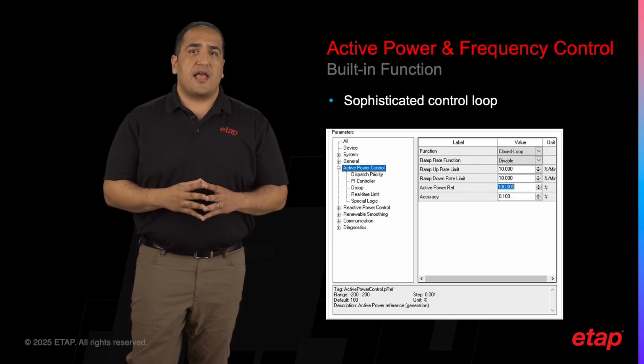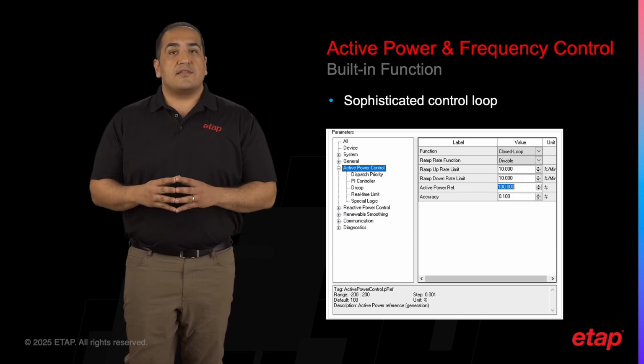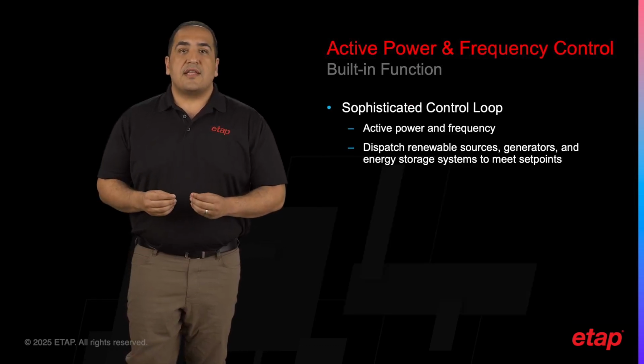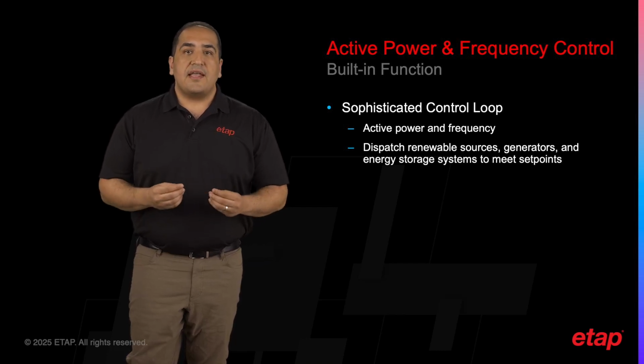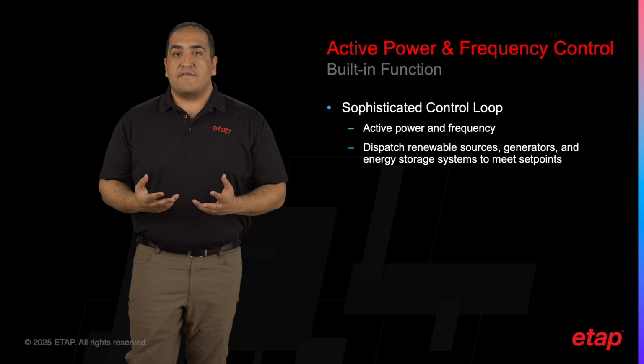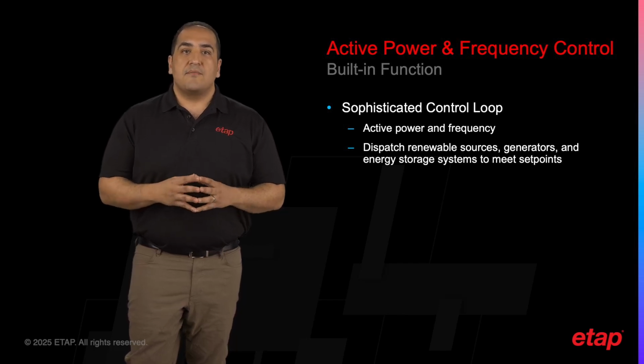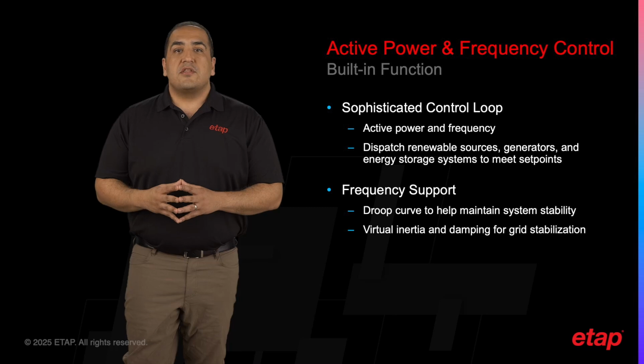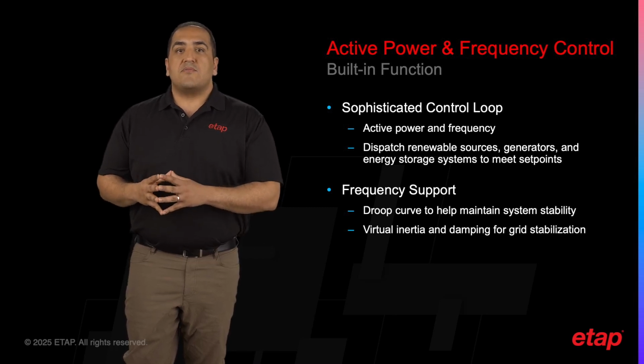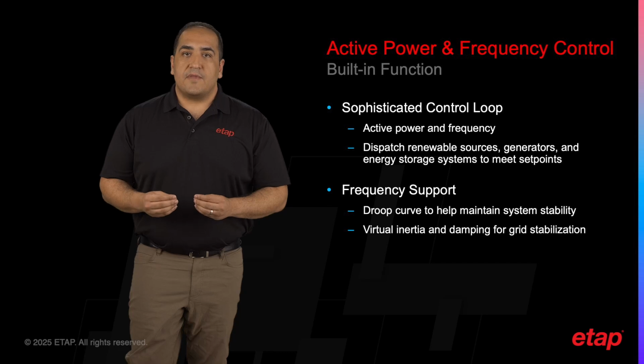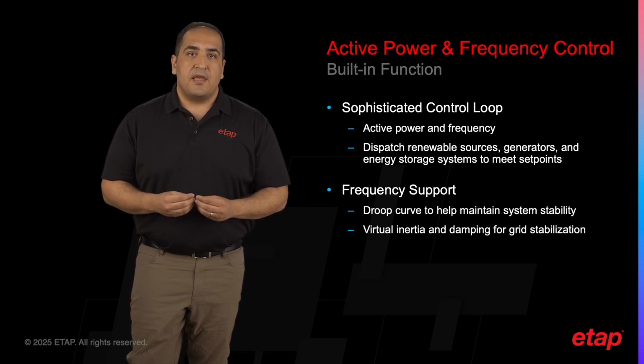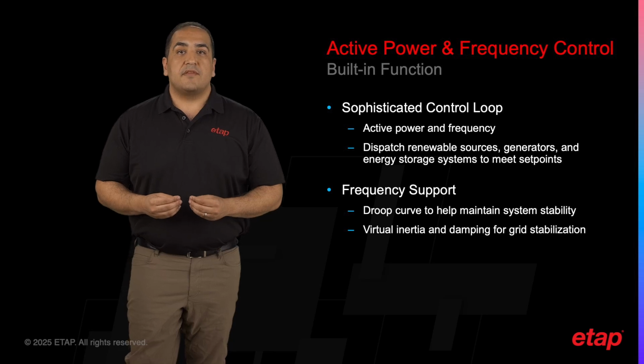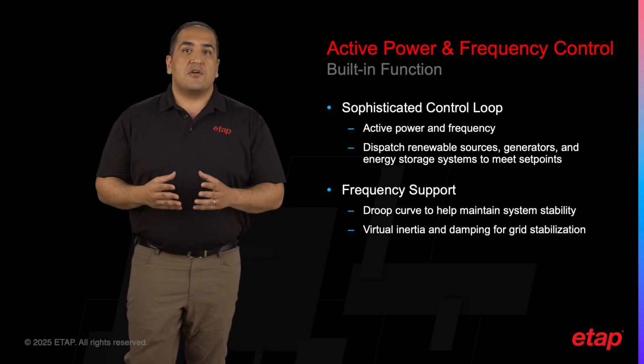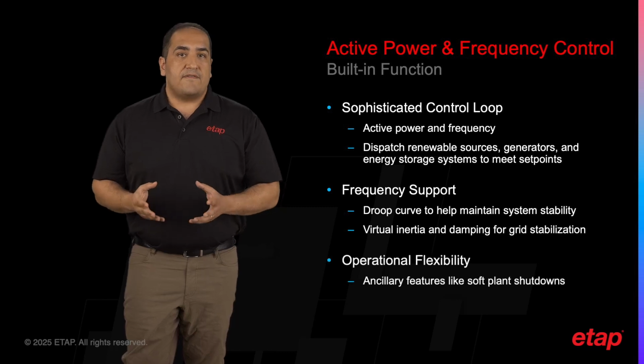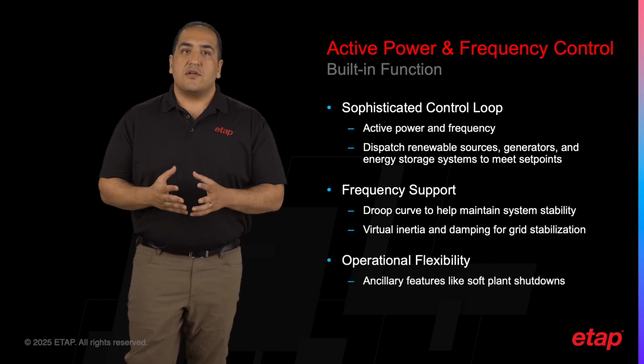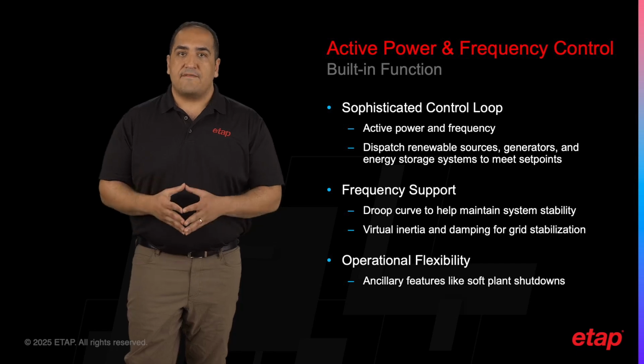EPPC excels in managing active power and frequency through a sophisticated control loop. It ensures that renewable resources, generators, and energy storage systems are dispatched effectively to meet the set point at the plant's point of interconnection. This function not only tracks the set point, but also provides frequency support using a droop curve, which helps maintain system stability. Additionally, EPPC can implement virtual inertia and damping, which are crucial for stabilizing the grid. Ancillary features such as soft plant shutdowns are also included to enhance operational flexibility and safety.